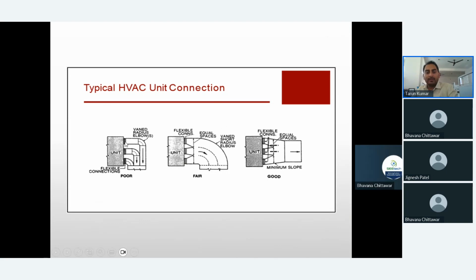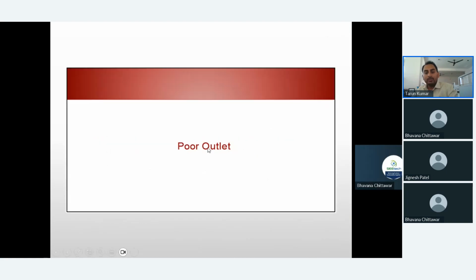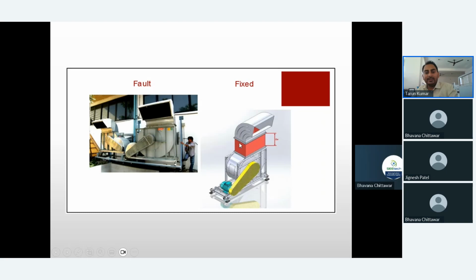Here what they did is make the plenum and take a branch, and all those bends were created. Instead, they would have done the branches first and then put up the plenum. You will get better flow performance when you put 2 or 3 fans in a single plenum. And here you see the poor outlet photograph we have put.